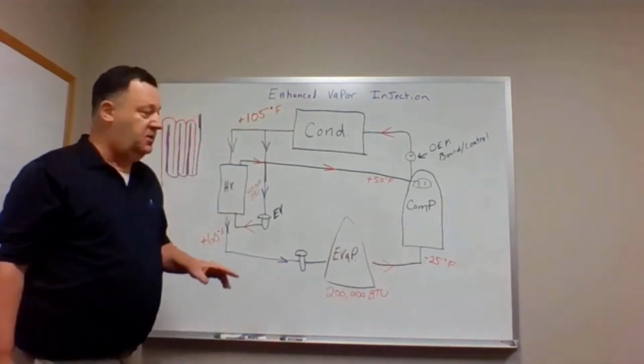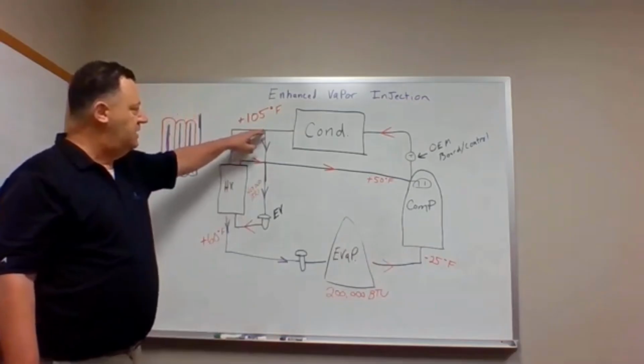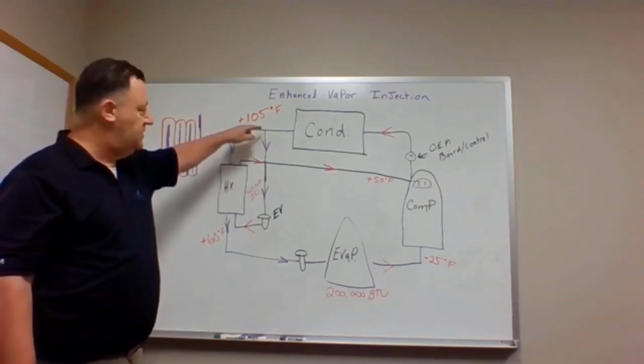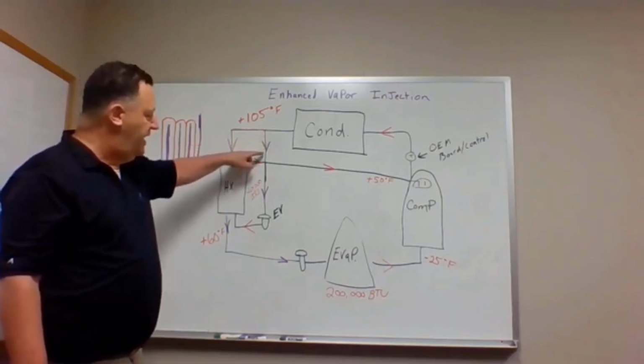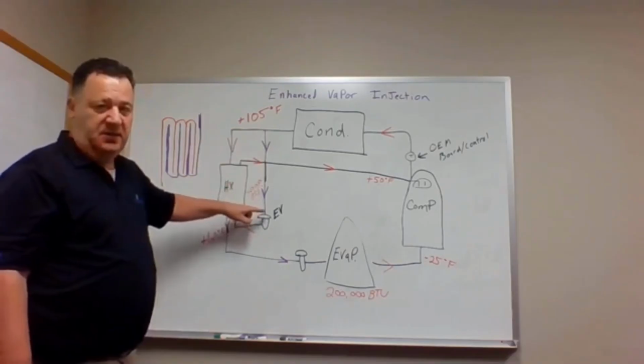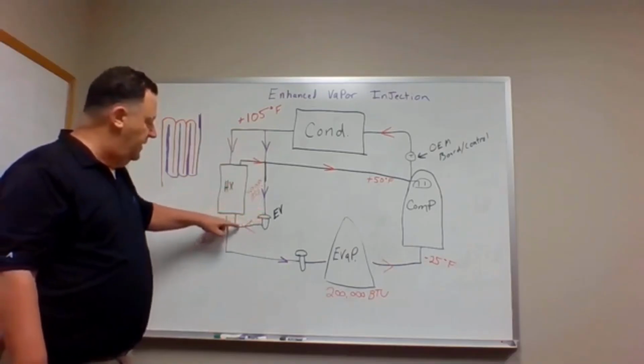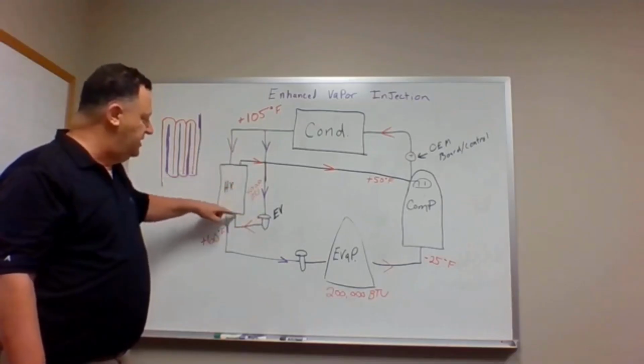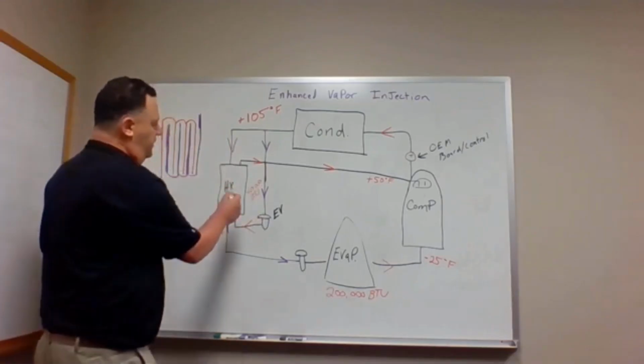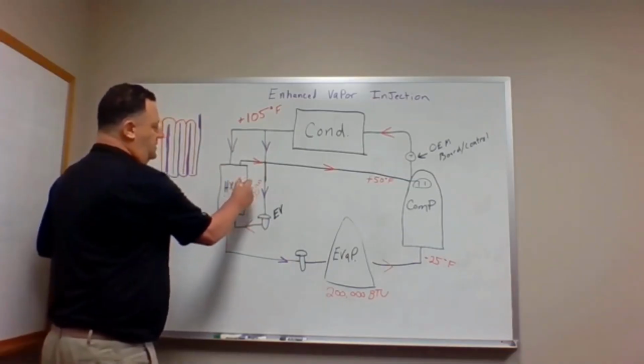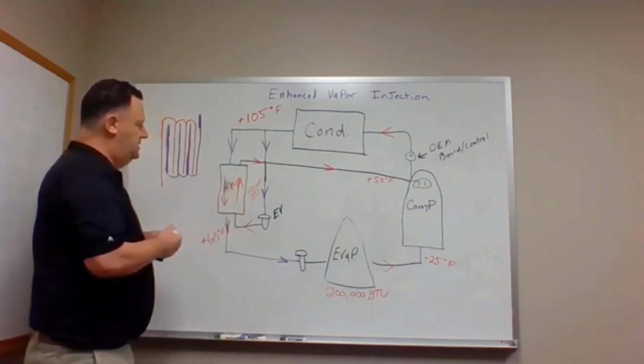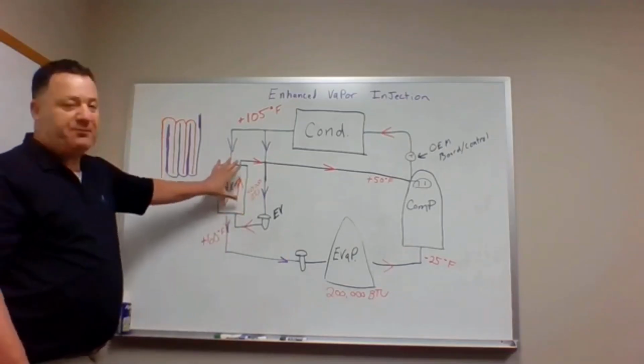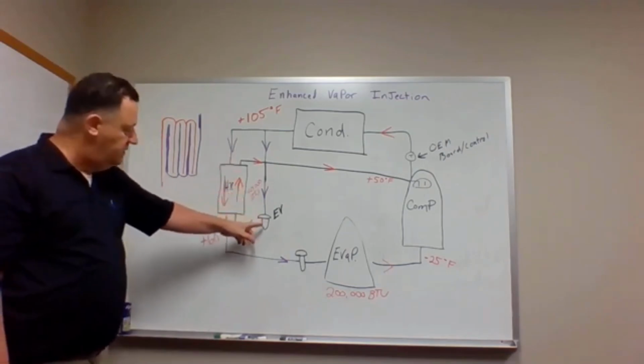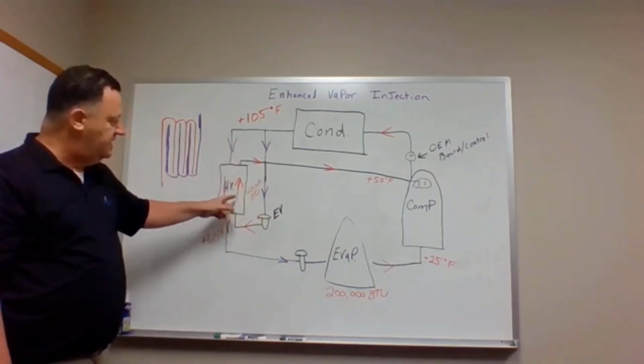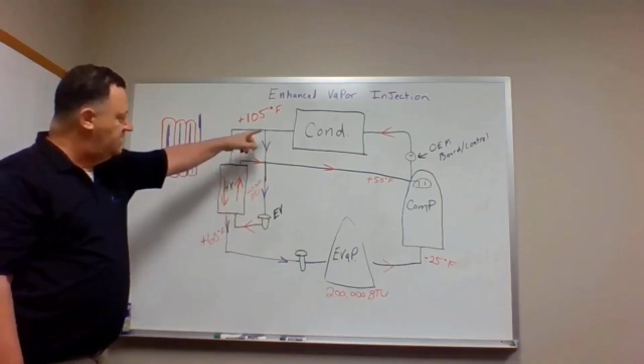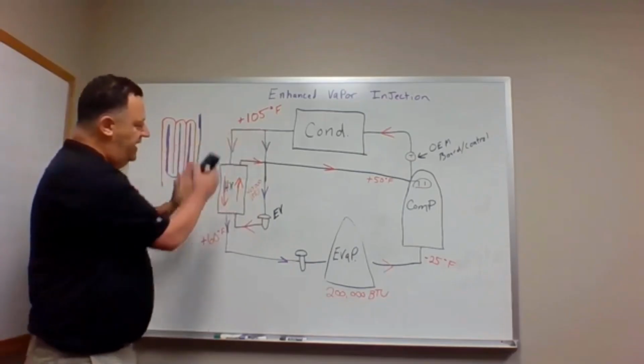Now, what I've changed here is I've branched off of this liquid line as we leave the condenser, and I've come down here to an EV, okay, to another metering device, and I'm coming through this brazed plate heat exchanger. By the way, these are counterflowed, okay? So these are counterflowed. So on one side, think of this as an evaporator on the right side. As it comes through this metering device, it now is a vapor, okay? And this is coming out of the condenser. It's a liquid. They're counterflowing.